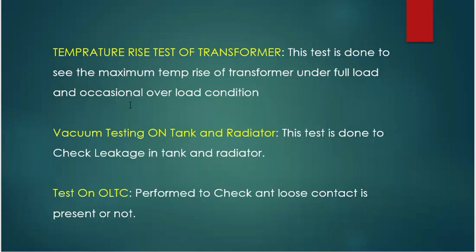Temperature rise test of transformer is basically a type test of transformer. This test is done to see the maximum temperature rise of the transformer under full load condition and occasional overload condition. This is an important test because if we don't know the maximum temperature rise of the transformer, we cannot design its insulation. The transformer windings are insulated from each other by means of paper insulation, and these insulations get deteriorated with the increase of the temperature.